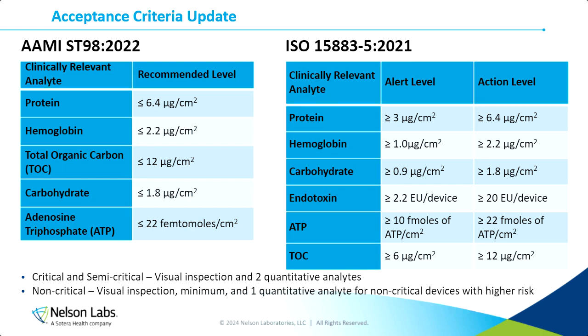And something to also bring up is critical and semi-critical devices. They need visual inspection after cleaning, and then we typically select 2 quantitative analytes. The most common we see are protein, hemoglobin, and total organic carbon, known as TOC. We don't see carbohydrates or ATP as often, but either way, when you're validating, you're going to want to have those 2 quantitative analytes for a semi-critical and critical device. And protein is going to be one that most regulatory bodies are going to want to see.